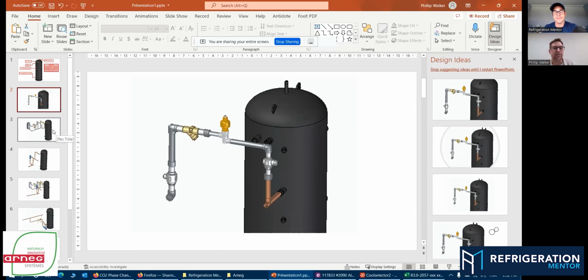It's been very well received to this point. We got 1 system up and running, another in pilot, and basically you have a manifold with some valves with a Belimo actuator. So the guys have been working with this for years, this type of technology, two-way Belimo actuator. It's just now it's stainless steel. So as we split condensers or split gas coolers, we split it in the same type of theory as we did with old condensers. Yeah. We can change over the manifold, because now we have a lot less mass flow requirement to satisfy the net refrigeration effect of the display cases.